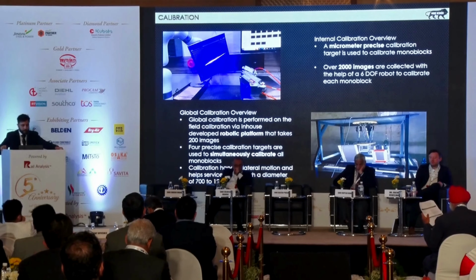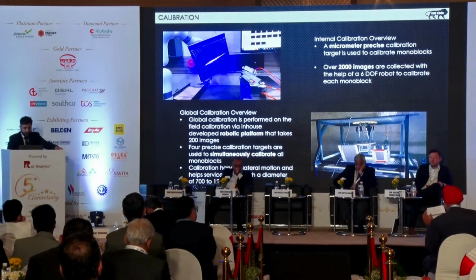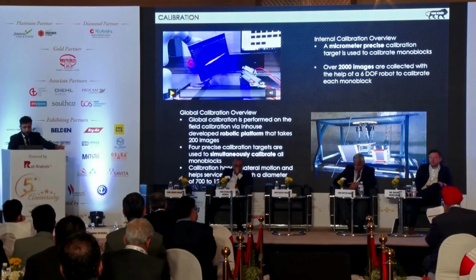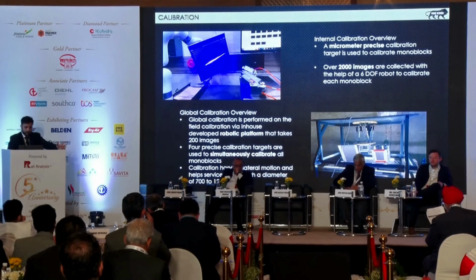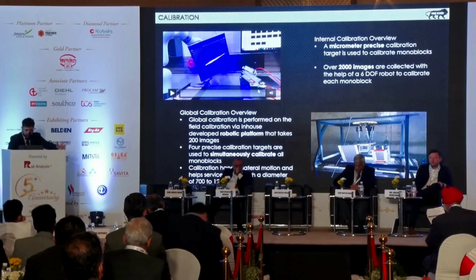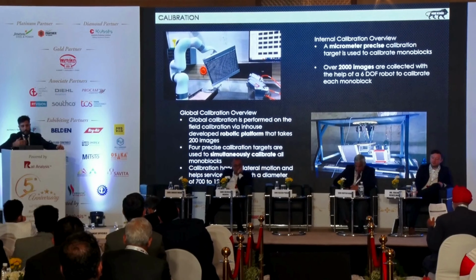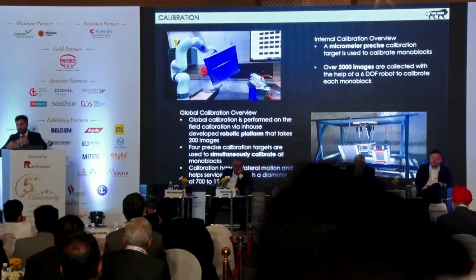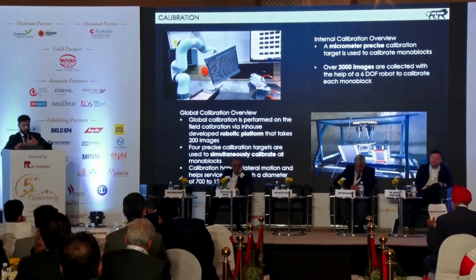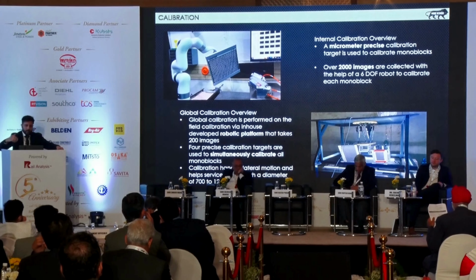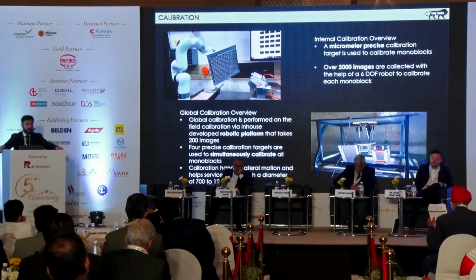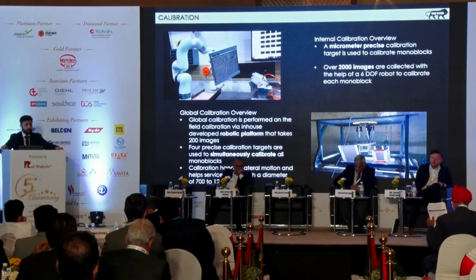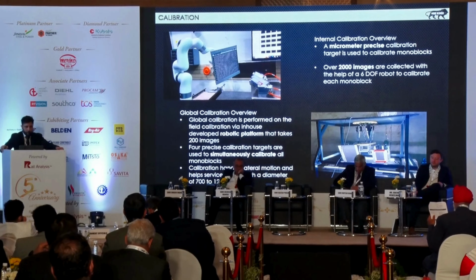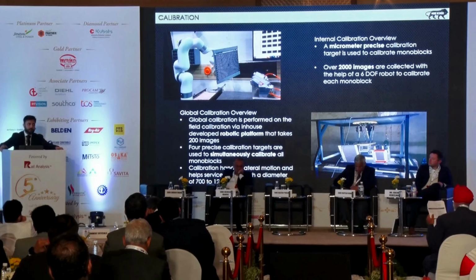And calibration is a pretty involved process. We have a 6 degree of freedom robot which uses a micrometer precise calibration target, and it calibrates our system by taking about 2,000 images. So it calibrates our cameras and lasers by essentially orienting the plate in the field of view of our cameras and lasers about 2,000 times. And this enables us to have a very, very high accuracy. So in the lab, we get about sub 100 microns of accuracy. Now, this is done in the factory before the system is sent out.